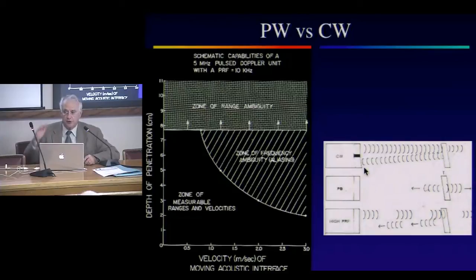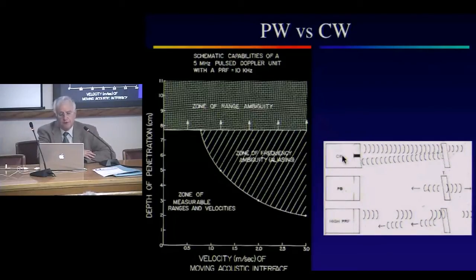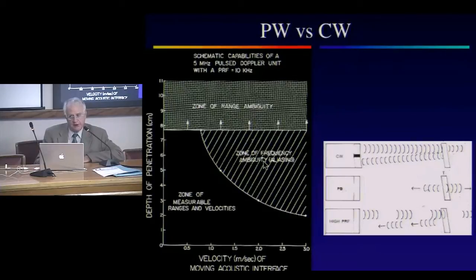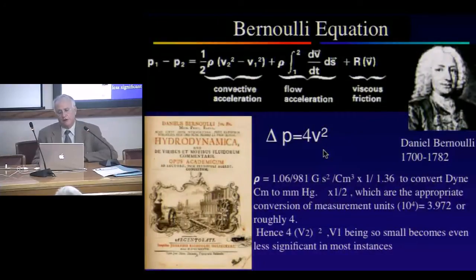The difference between pulsed wave and continuous wave Doppler is that pulsed Doppler is range specific while continuous wave Doppler — because it doesn't rely on a pulse signal — is frequency specific but range ambiguous. So you have a choice of either frequency or range specificity depending on which modality you use.